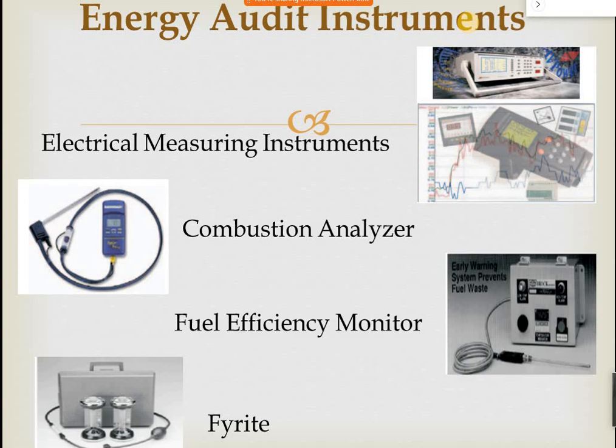Okay. So electrical measuring instrument. First one. Electrical measuring instrument. We can see here this is the electrical measuring instrument, and this instrument used for measuring major electrical parameters like kVA, kW, PF, Hertz, Ampere, and volt. In addition, some of these instruments also measure harmonic, and these instruments are applied online. Okay. So another one is combustion analyzer.